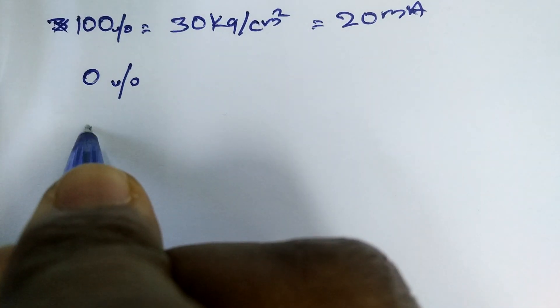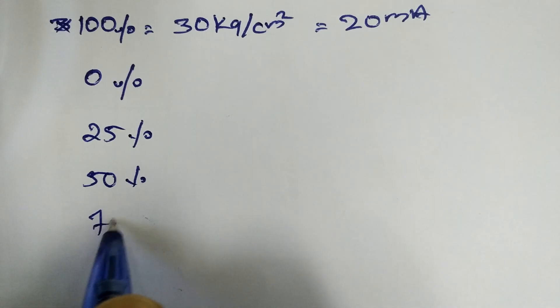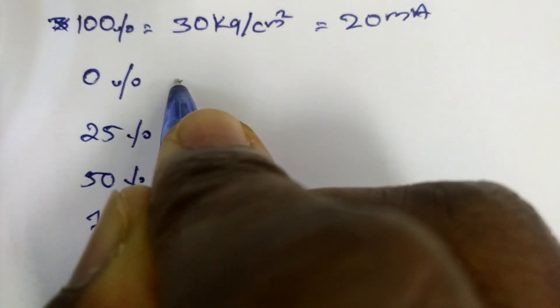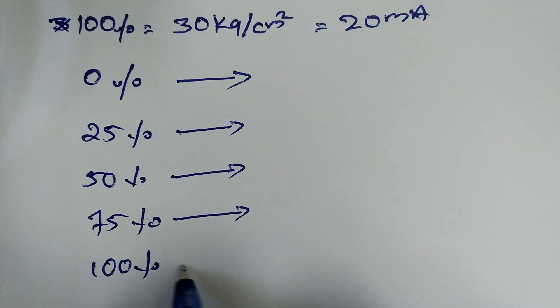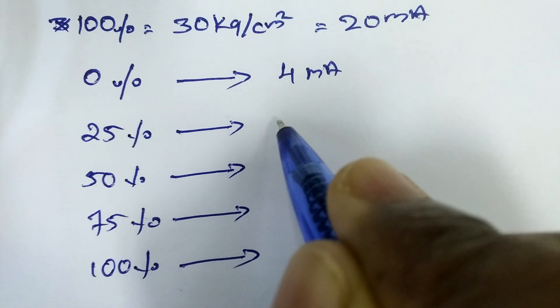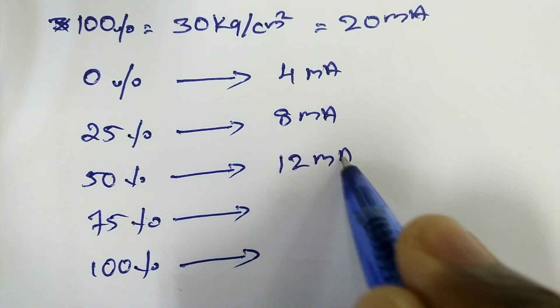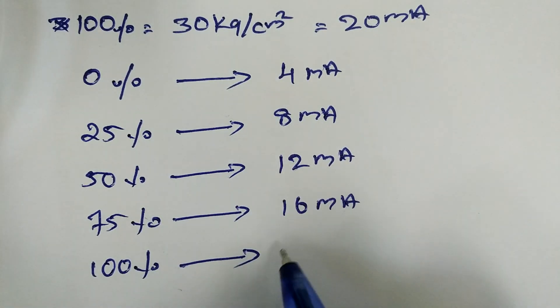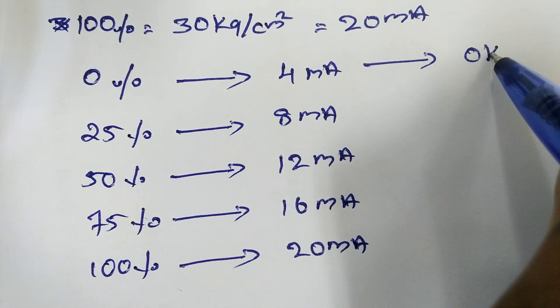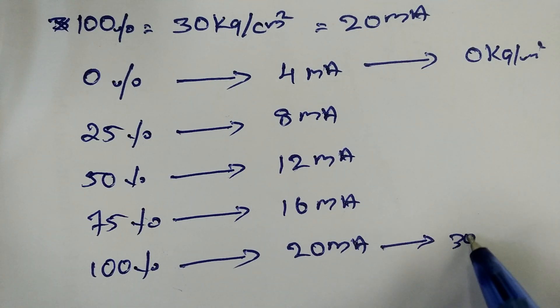We use calibration at 0%, 25%, 50%, 75%, and 100%, with their corresponding milliamp values. These are standard values: 0% = 4 mA, 25% = 8 mA, 50% = 12 mA, 75% = 16 mA, and 100% = 20 mA. The pressure range is 0 to 30 kg per cm².